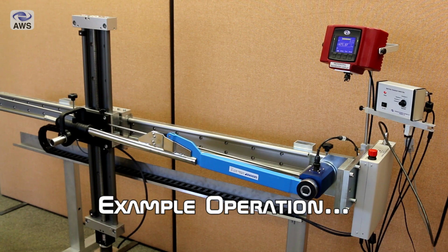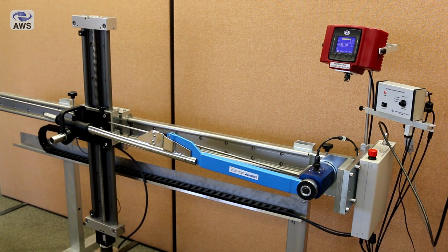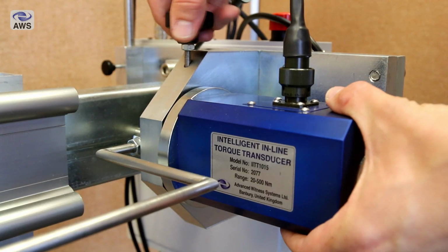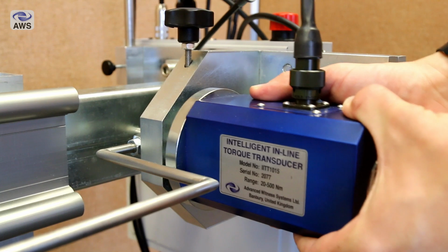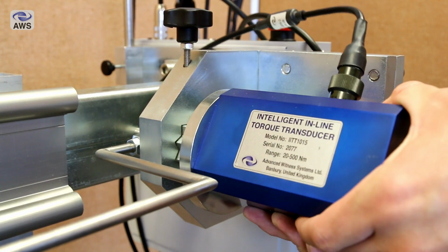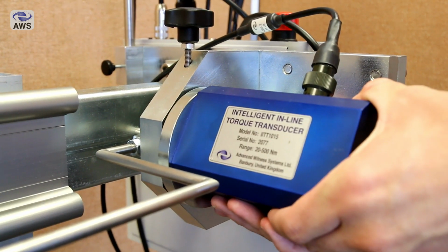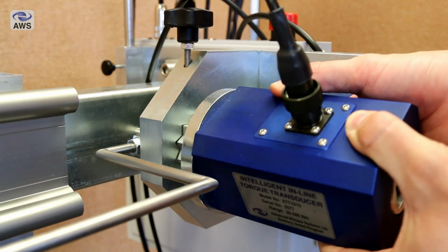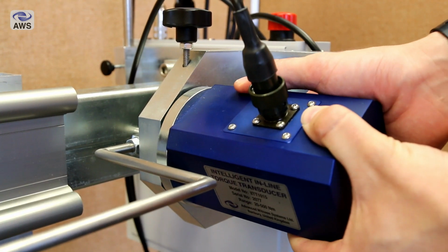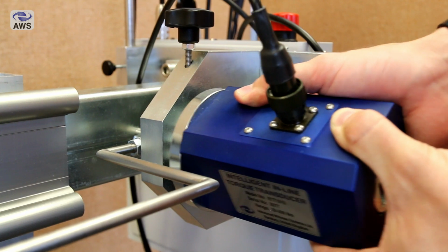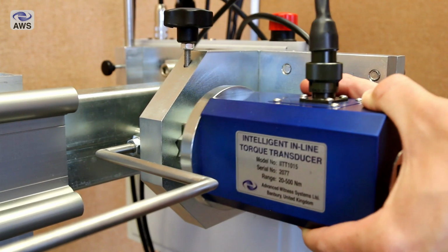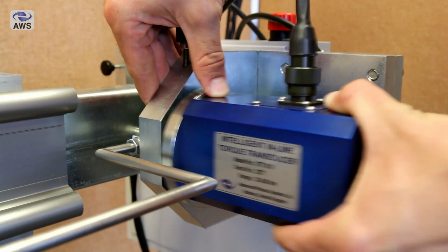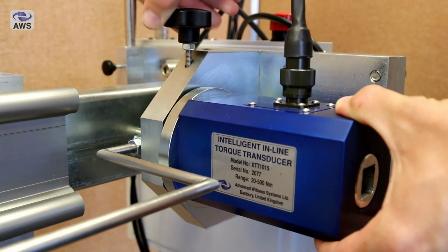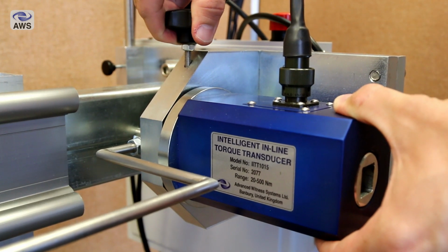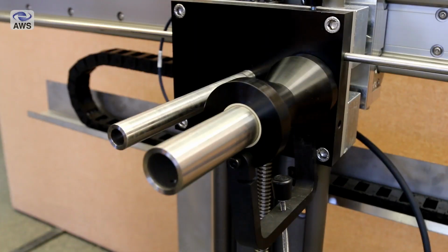In this example, we're using a breakback wrench, a click type wrench. So firstly, you select the transducer that you want to use with the torque wrench. These can either be our Intelligent Inline Torque Transducers or another manufacturer's transducers using our Intelligent Instrumented Transducer cable, which converts them to the CAN bus signal required to operate with our machine. The transducers can be stepped around 30 degrees to solve any alignment problems with fixed square drives on torque wrenches.